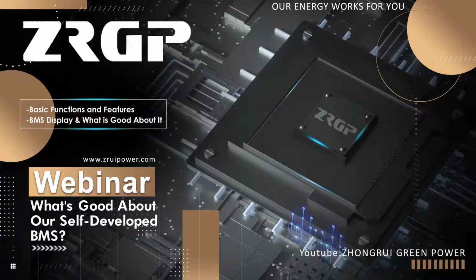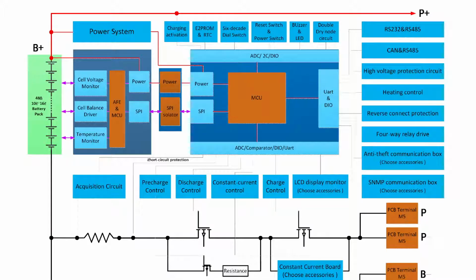So let's see the structure of the BMS. Here is the structure of the BMS, and I'll talk about some functions it has. So first, the BMS is equipped with charge and discharge current detection, charge and discharge overcurrent alarm and protection functions. The charging current is displayed as positive. The discharge current is displayed as negative. And the current sampling accuracy at 25 degrees can reach less than 2% at FS.